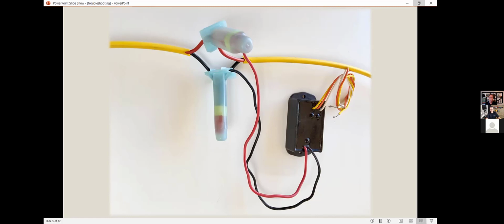So fundamentally, it would be important to look at the message and specifically at the words in the message to understand whether the problem is on the solenoid side of the system or whether it's a two-wire message. Good point. If it's a solenoid message, we don't want to chase down taking apart two-wire splices. Because if it's a solenoid issue, you could actually ignore it and just say, I'm going to manually water it. Well, if it's a two-wire issue, you're going to manually water your whole site. So just keep in mind that the error message on the baseline controller will tell you there's a two-wire error, overcurrent, or the device is no longer communicating, which is a two-wire issue, or whether it's a solenoid side, so that you can start your troubleshooting tree in the right direction.